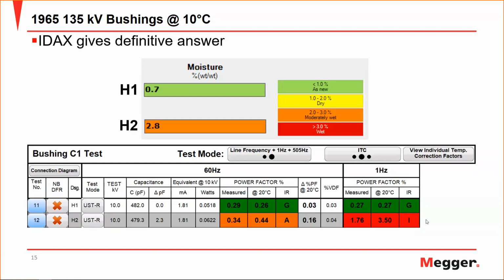But let's say that you found this problem with this bushing here, but the customer does not have an extra 115 kV bushing laying around to install. Well, it's better that they know now that they have to order that bushing than if they were to just continue on as if everything was perfect and then all of a sudden had a bushing fail. Now what are they to do? They may not have 6 months to wait around for a bushing, so they have to scramble and get a temporary substation in. Who knows? So what is the next action when you have bad 1 Hertz? Well, it really depends on what the customer is expecting from this particular asset and what they have available to them. Do they have an IDAX on site? Well, that'd be great. Then I would do an IDAX 100% for sure if you have a bad or high 1 Hertz power factor, because it will tell you exactly what's wrong with it, and it will tell you how bad it is.